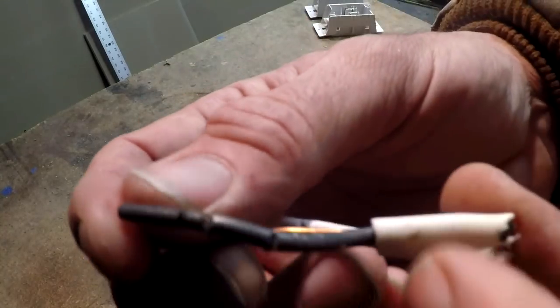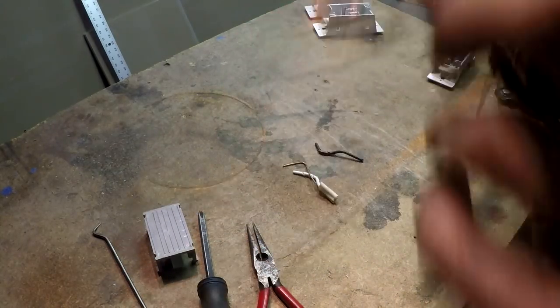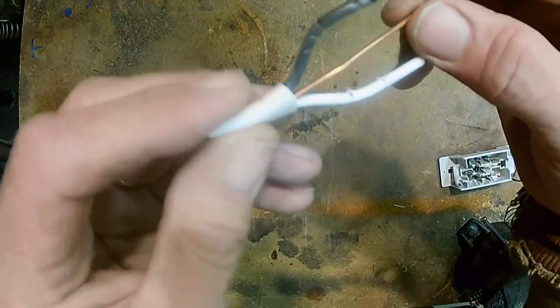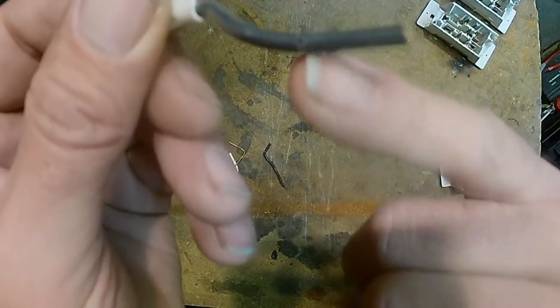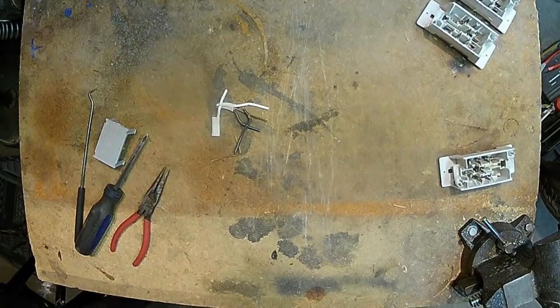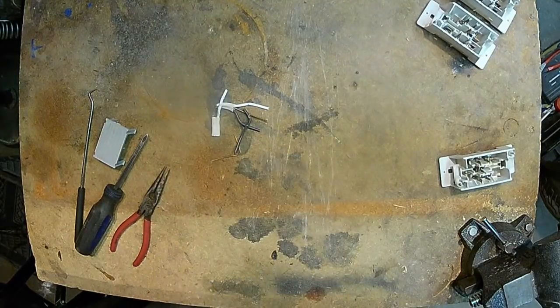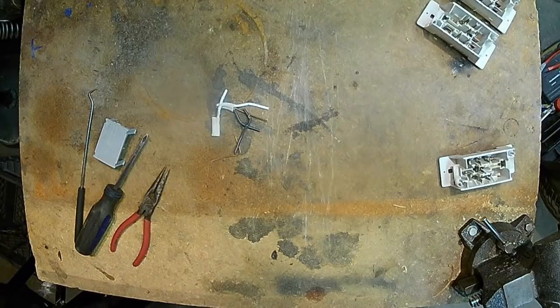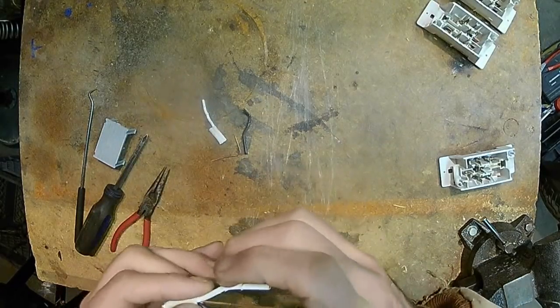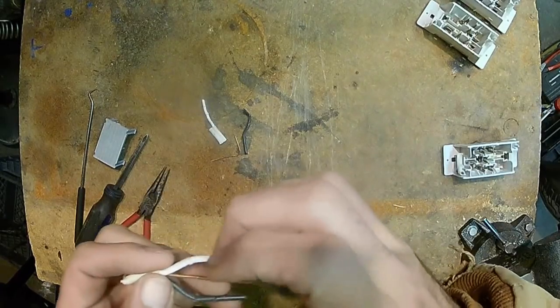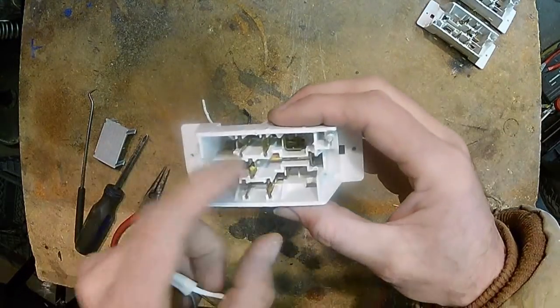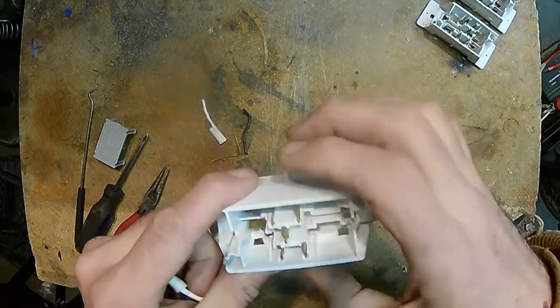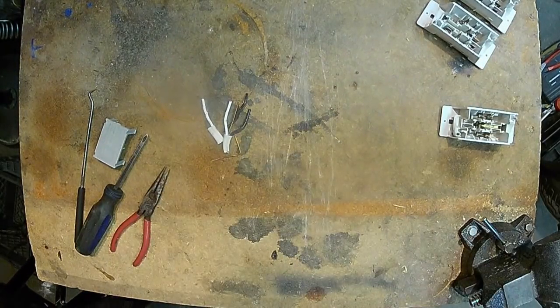Right there is all the contact that was made on that wire. Just that little cut right there. So over time, if you put anything that draws a heavy load, a small space heater, a crock pot, or anything like that, the volts, the amps drawn through it, and the resistance from this, from your wires to your box, are actually going to heat up. And over time, it'll cause it to fail.